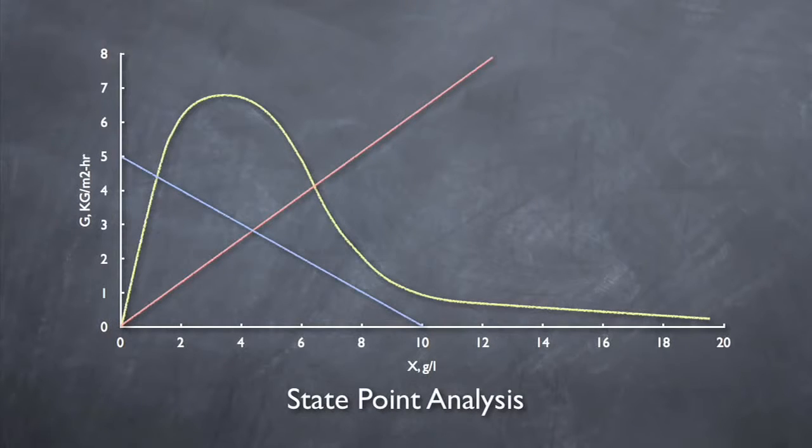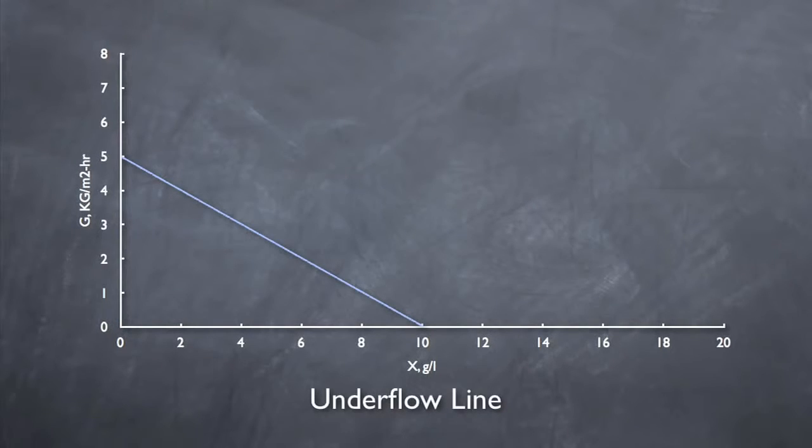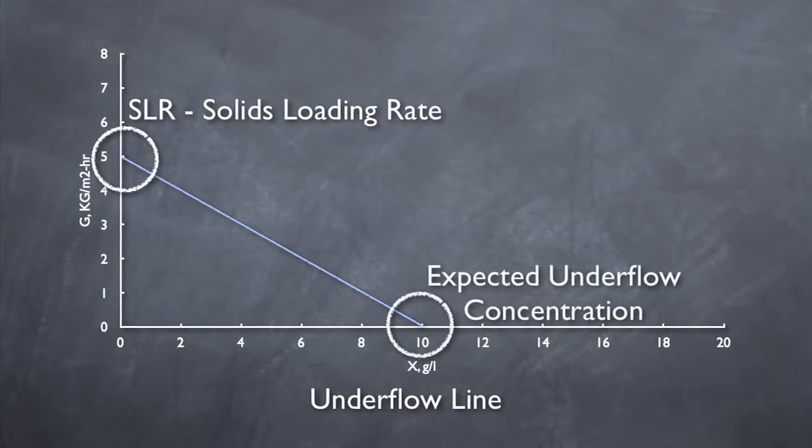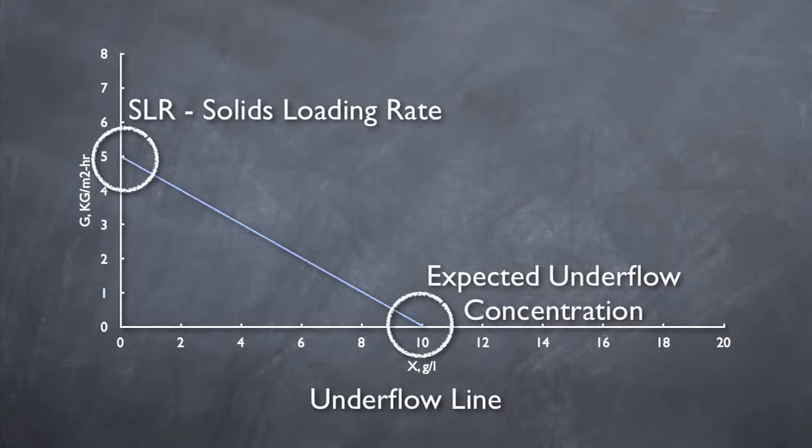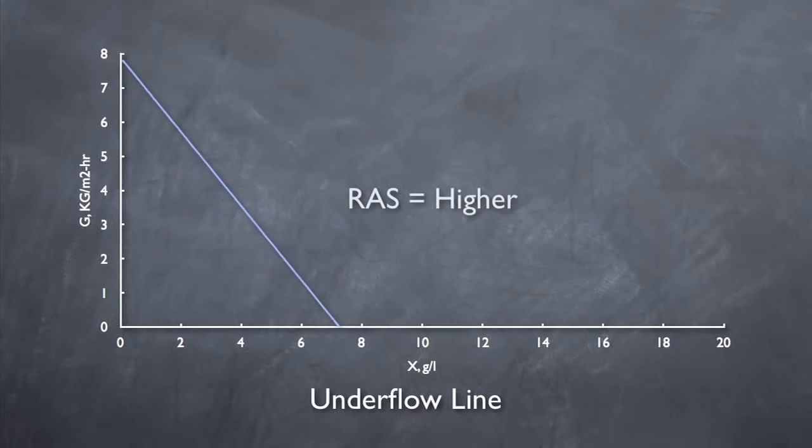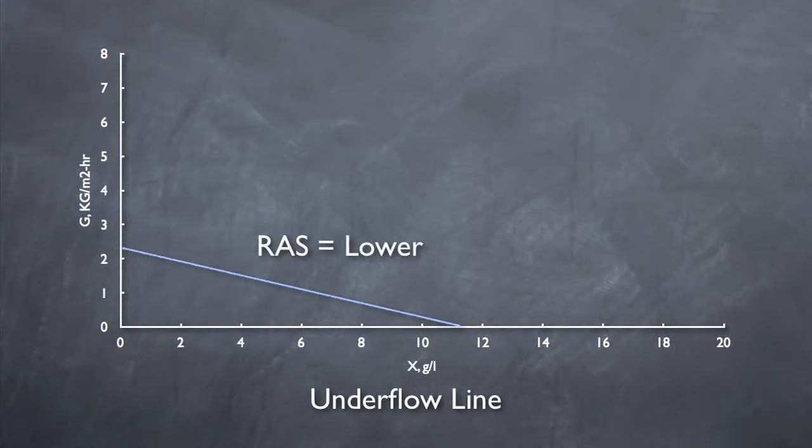The third and final component of the state point diagram is the underflow line. The y-intercept of this line represents the solids loading rate, or SLR. The x-intercept of this line represents the expected underflow concentration. The slope represents the solids underflow rate, or SUR, which is calculated by dividing the RAS flow by the clarifier surface area. This line can be adjusted in two ways. First, by changing the RAS rate, you can affect the slope. A higher RAS rate will result in a steeper slope down. A lower RAS rate will result in a flatter slope.